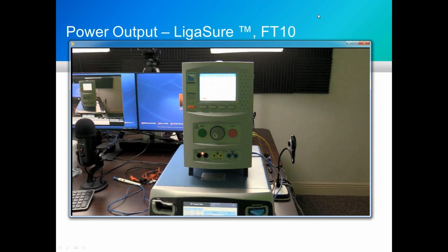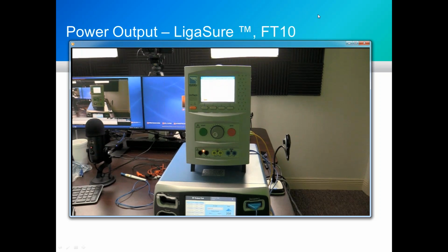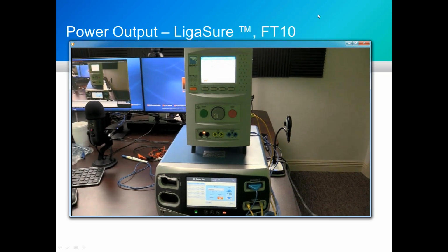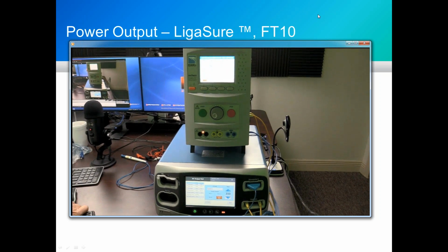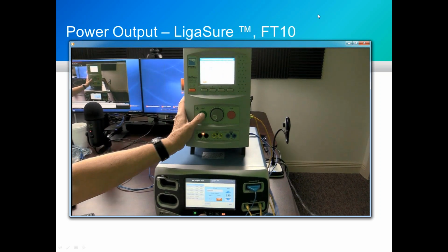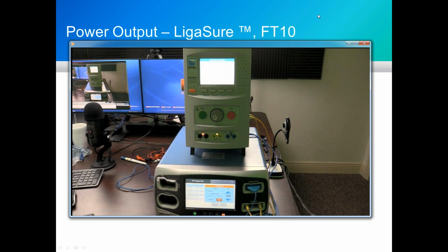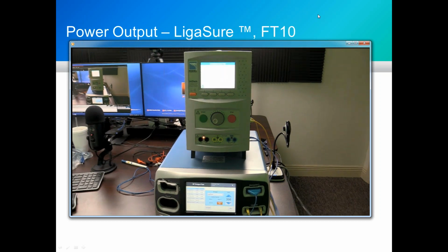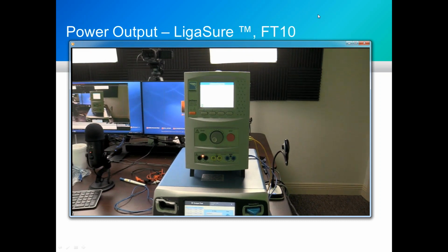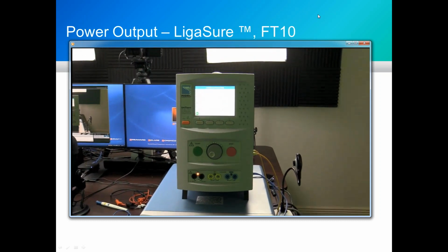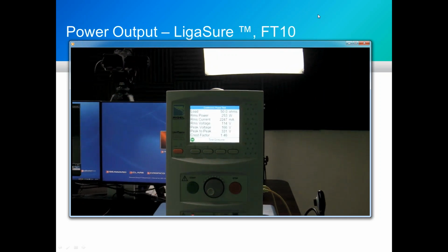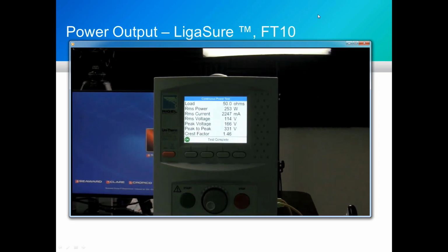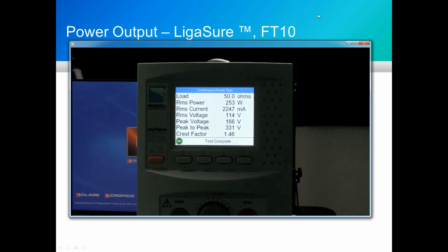And again, what we're really setting here, we're setting a DC resistance. But what we'll see on the display of the FT10 itself is what the unit is seeing, what the generator is seeing for the actual impedance. And we measure 2.2 and a half amps.